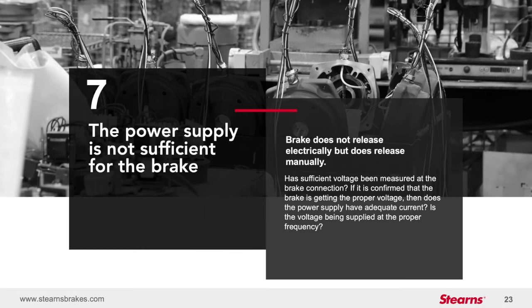Mistake number 7, the power supply is not sufficient for the brake. I get calls from time to time from people who have experienced issues where the brake doesn't release electrically. It releases manually, but when they put power to the brake, it doesn't release. Or the brake releases and the motor's driving and they're running their operation, and then somehow in the middle of the operation, the brake unexpectedly engages as if power was removed. They check their panel, and the panel says that the brake is getting voltage.